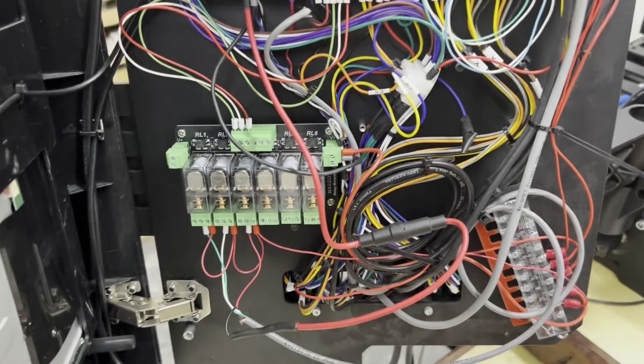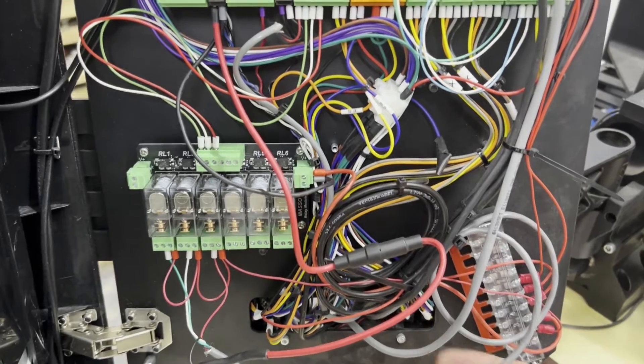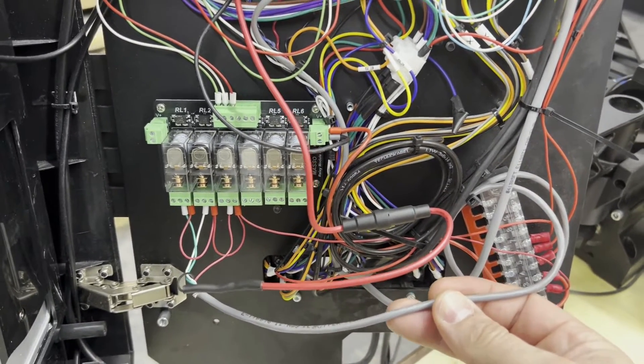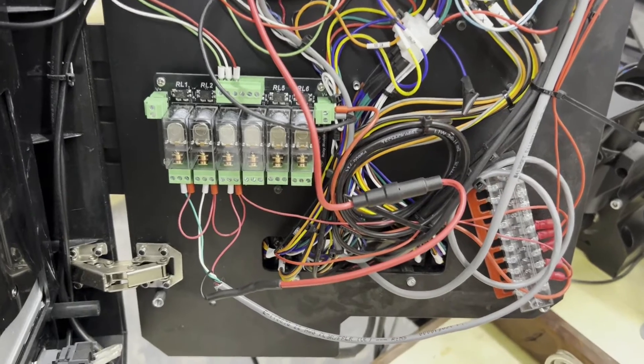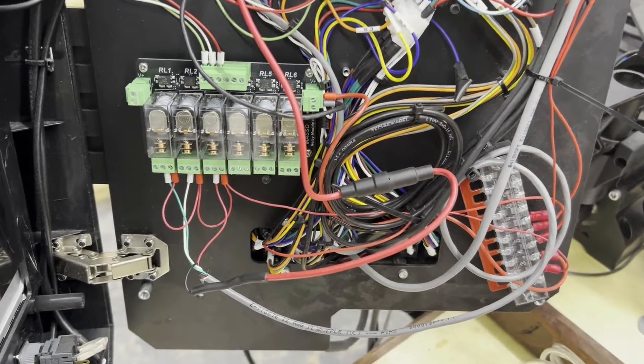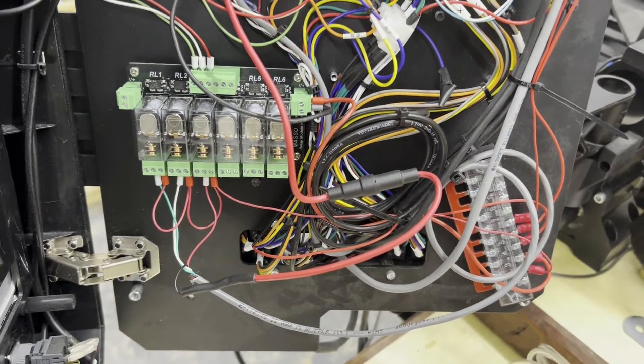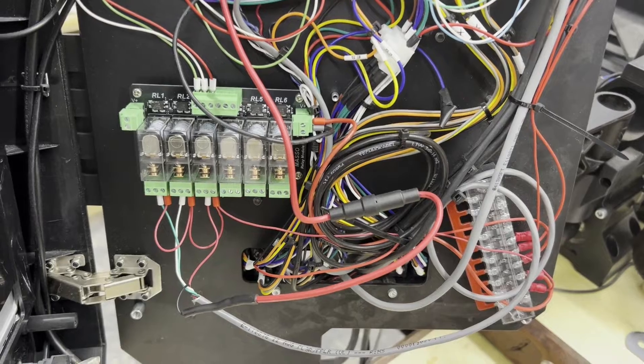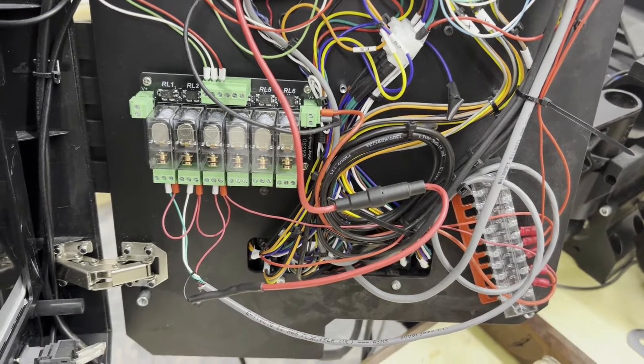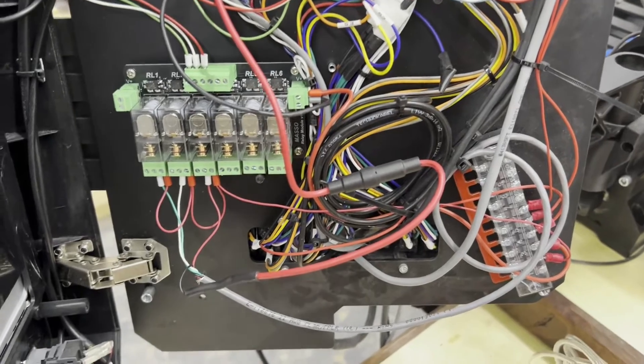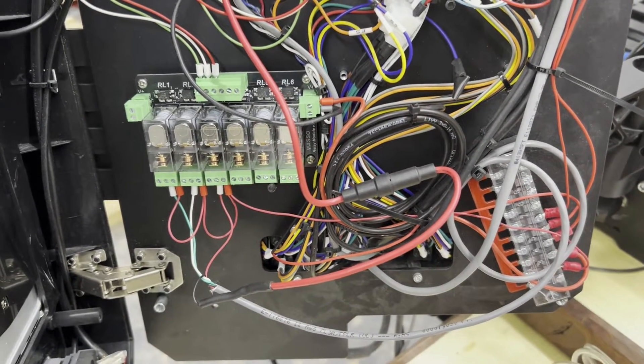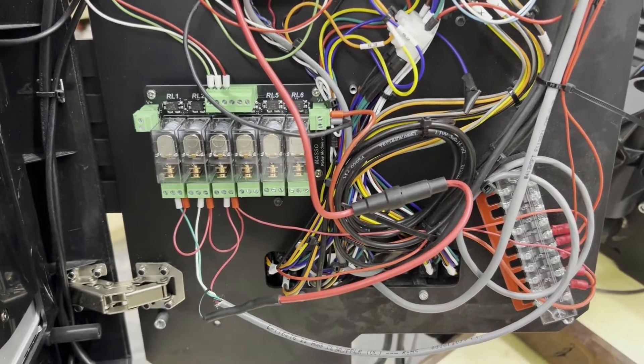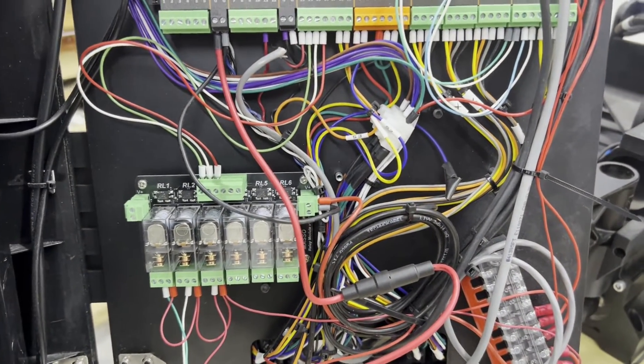Now, that 22.4, let's hold there for just a second. I just used some 22.4 I had laying around and it's nothing special. If I was going to buy something specific for this job, I'd probably buy shielded, plenum-wrapped cable. And I'll link to some of that as well. But, really, you don't have to get fancy. Any 22.4 is probably going to work. It's just a little bit safer option to use the shielded and plenum-wrapped, both from a fire perspective and from an EMI perspective. But, you know, it's just a tower light. I'm not worried about what happens if it acts funny. So, any old 22.4s probably do fine.